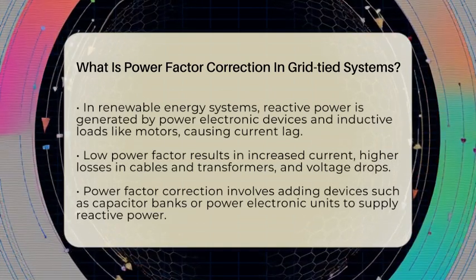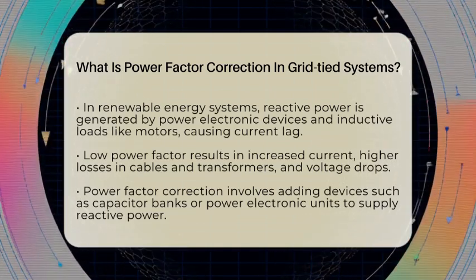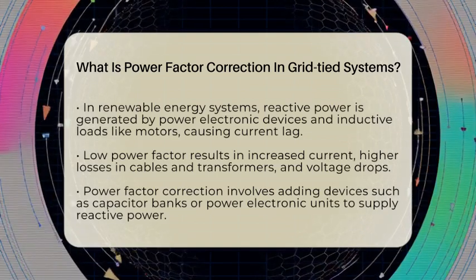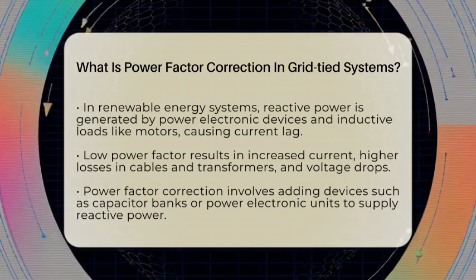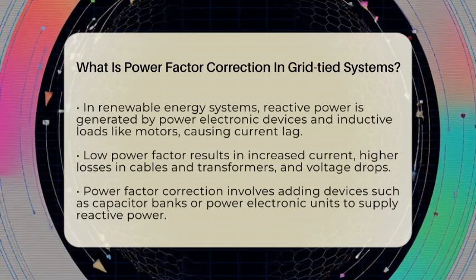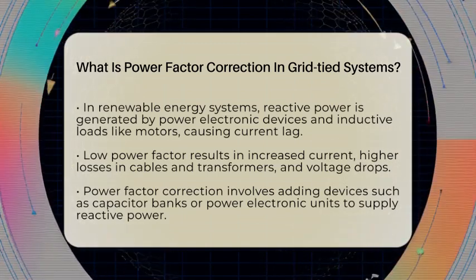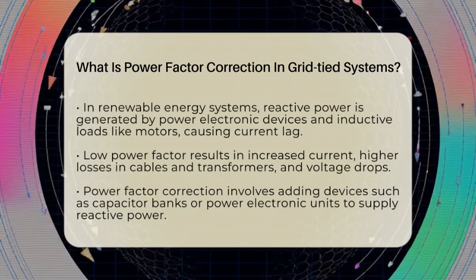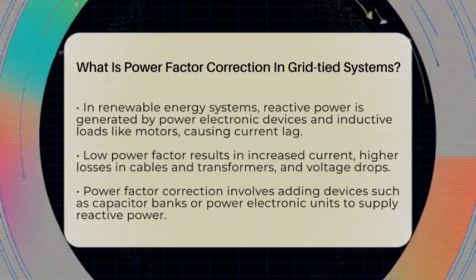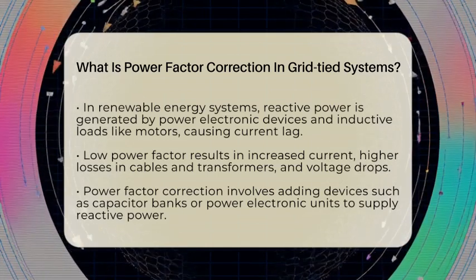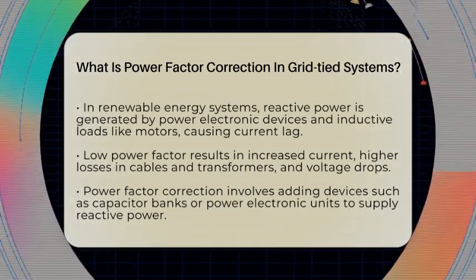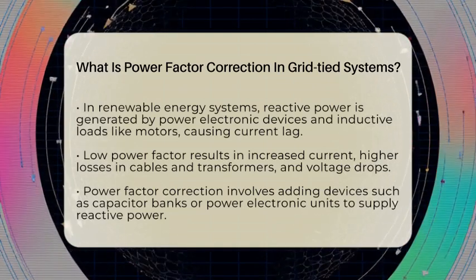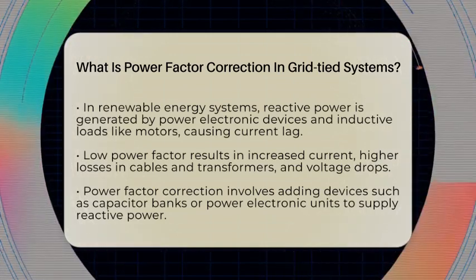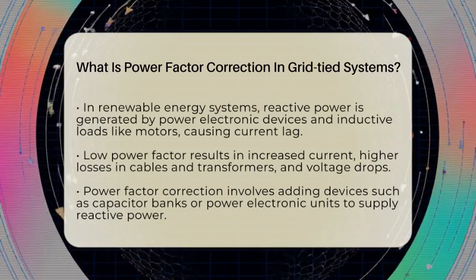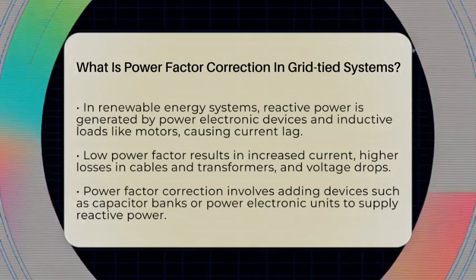Power factor correction helps fix this issue by adding devices that supply reactive power to the system. These devices are usually capacitor banks or advanced power electronic units that produce leading reactive power. By doing this, they offset the lagging reactive power caused by inductive loads. The goal is to bring the power factor closer to 1, which means more of the electrical power is used effectively. In practical terms, capacitor banks are connected in parallel with the load, either in single-phase or three-phase systems.